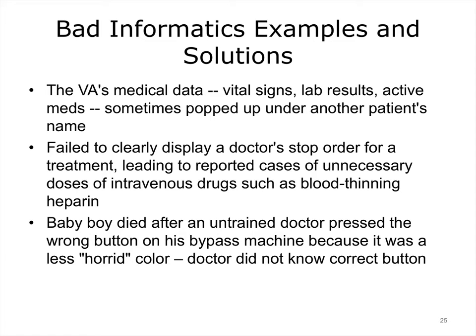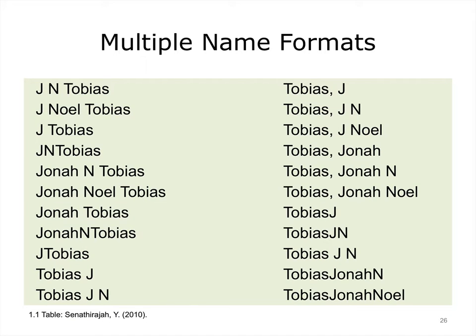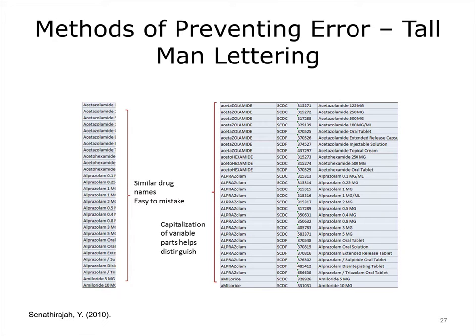There are many examples of bad design. One describes a problem with VA medical data in which data sometimes popped up under another patient's name. Other examples include failure to clearly display stop orders leading to unnecessary drug doses, and a fatality after an untrained doctor pushed the wrong button. Multiple name formats are just one of the design issues that must be addressed carefully. Drug names with their common stems and varying suffixes are another, because of the similarity in names and the fact that in alphabetized pick lists they will appear together, increasing the risk of the wrong drug being selected.